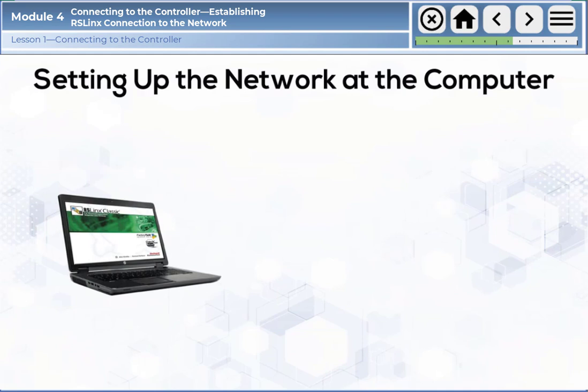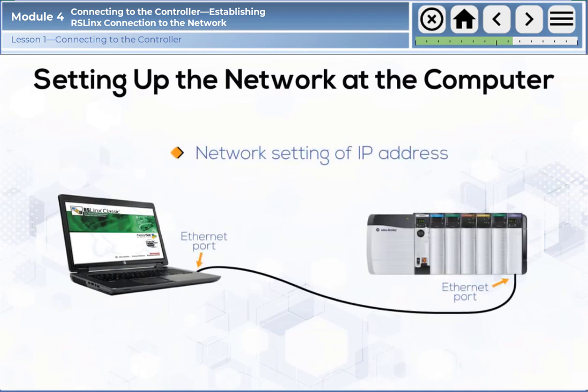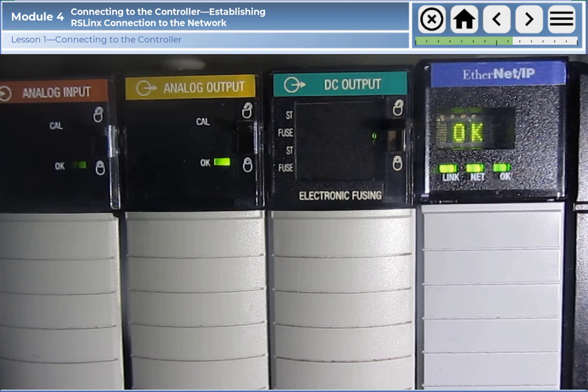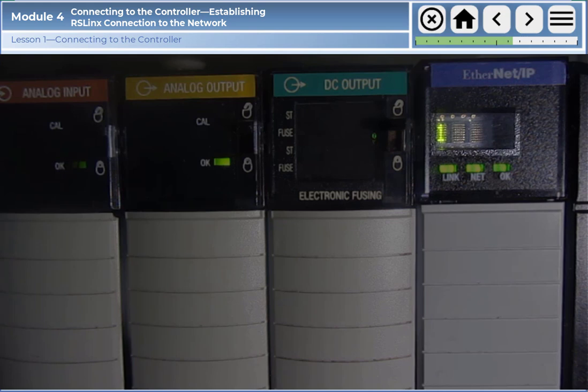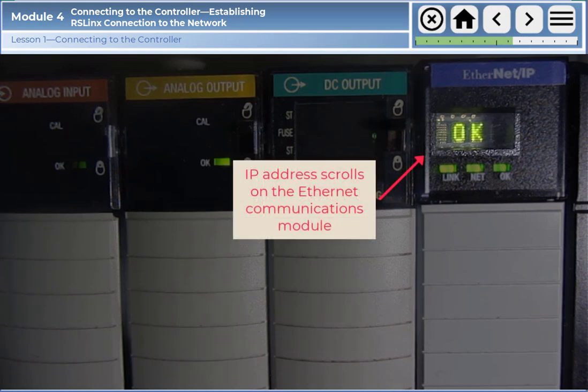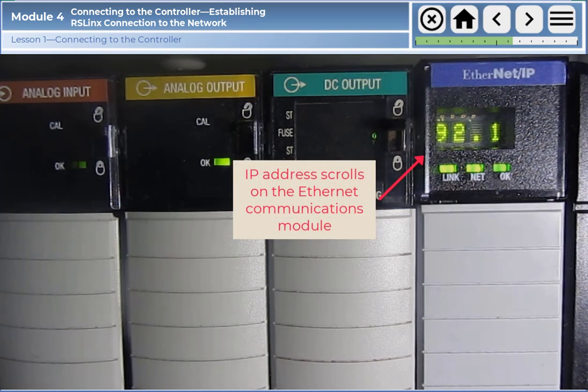The network settings involve the assignment of Internet Protocol, or IP addresses, to the computer's Ethernet port or connector, and also to the Ethernet communications module. Think of the IP address as a unique phone number where two parties can connect, in this case via the Ethernet network. The IP addresses for the communications module in the ControlLogix chassis will most likely be defined by the programmer and will show on the scrolling display of the Ethernet module.